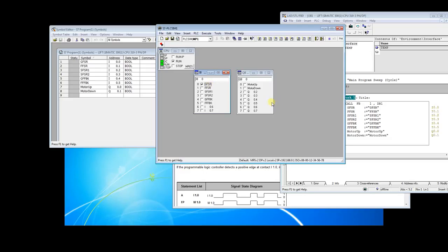Okay, so everything is fine, but let's see how the safety sensors work. So let's send the lift upstairs again. The ground floor sensor and feedback are needed. Okay, and now let's simulate sensor 2, as I remember, and the lift should stop. Generally it should stop if I select sensor 1 or sensor 2. So let's see sensor 2. Yes, the lift doesn't work now, so everything is okay.